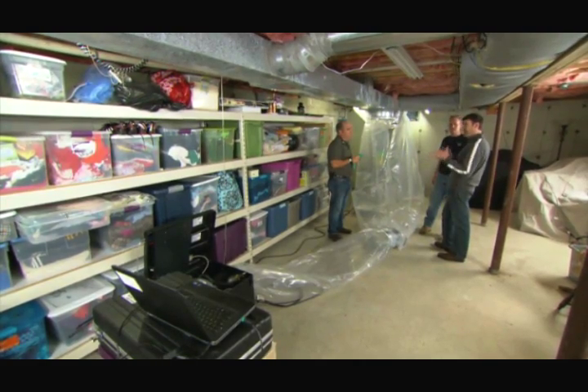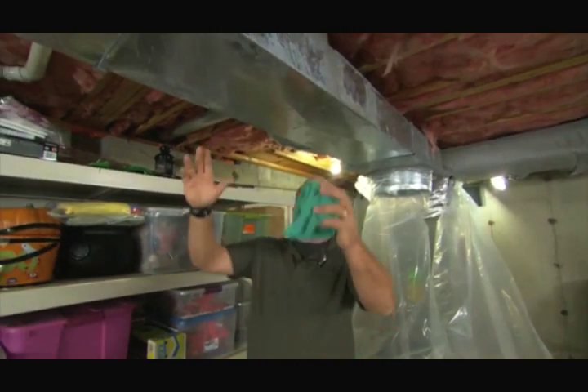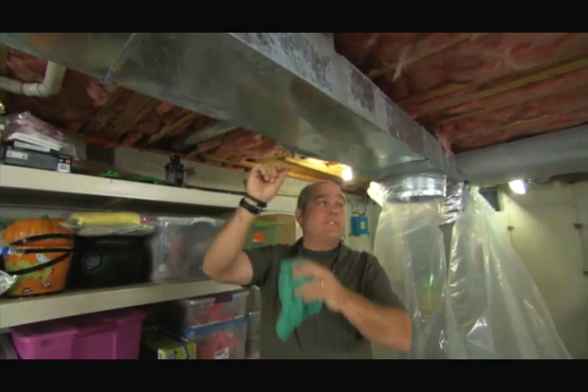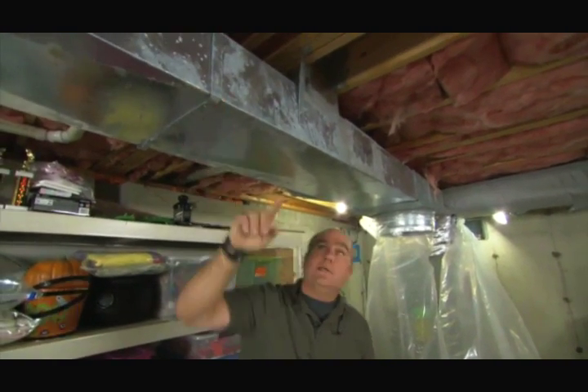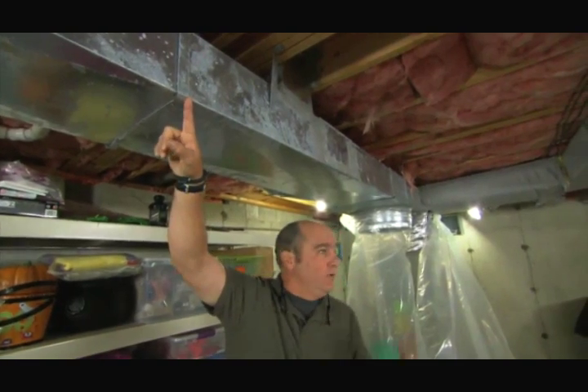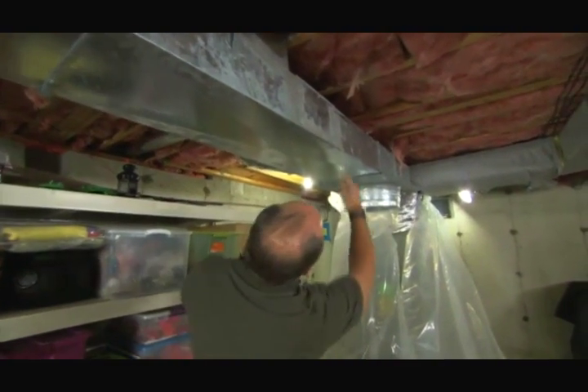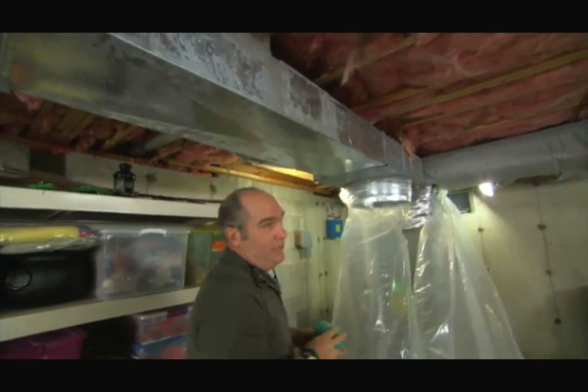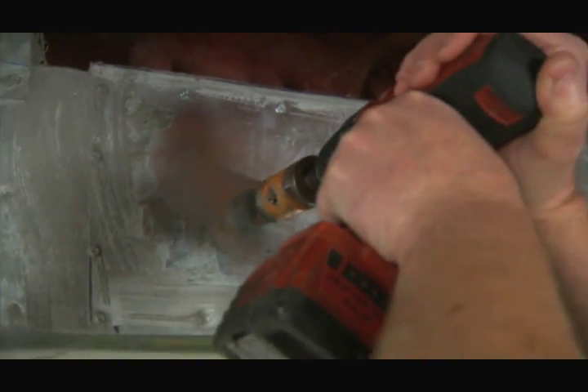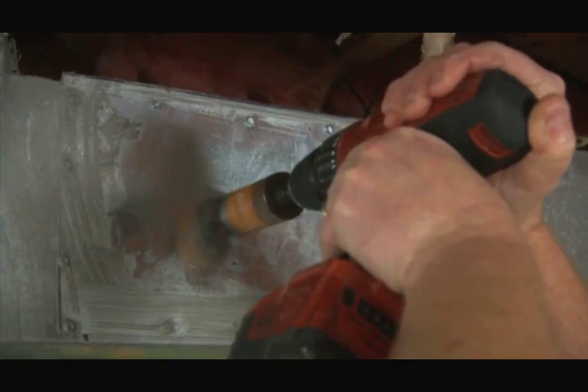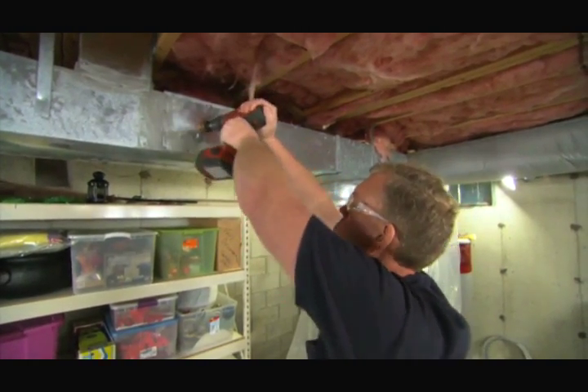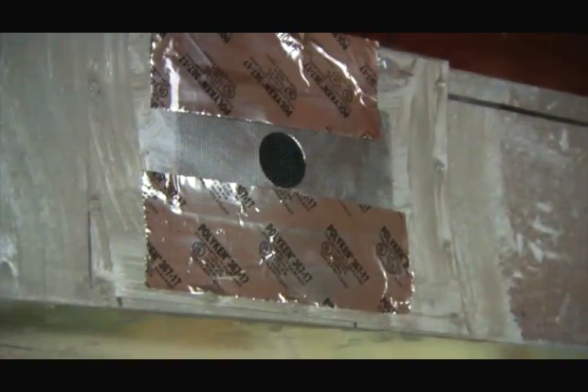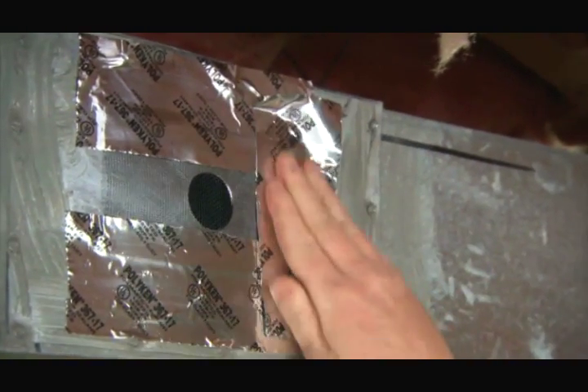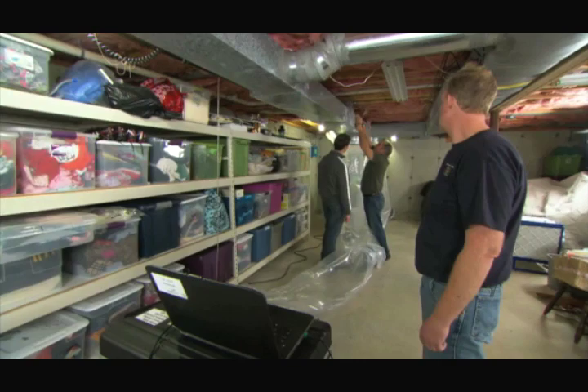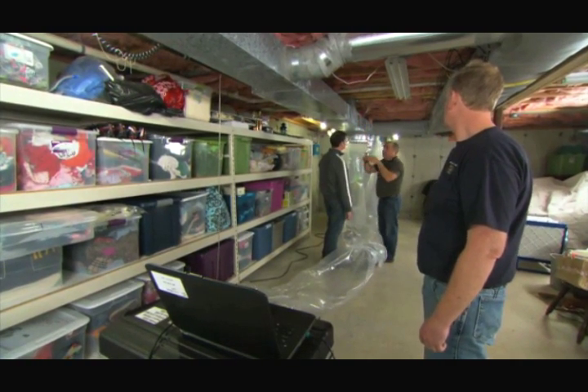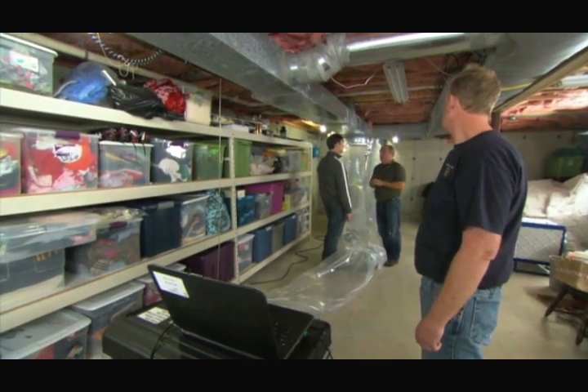Okay. So all this happens from inside the ducts? It does. We're not going to actually line all the ductwork. We're only going to seal where the breaches are, the breaks in the ductwork. So we might see a little bit leaking out from right here. In order to prove to you how it works, we're going to cut in a hole right here with a screen to really see it at work. Great. So with this hole and the window screen over it, I've simulated some of the duct leakage you have upstairs in the building. So we all set to go, Steve?